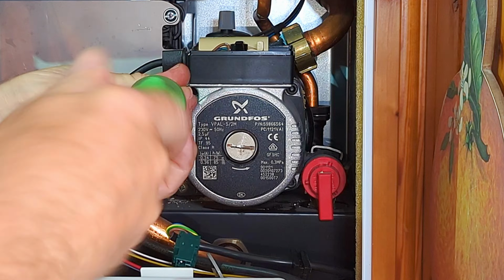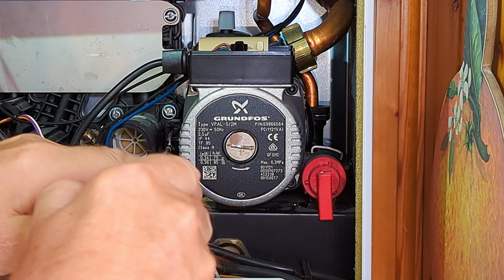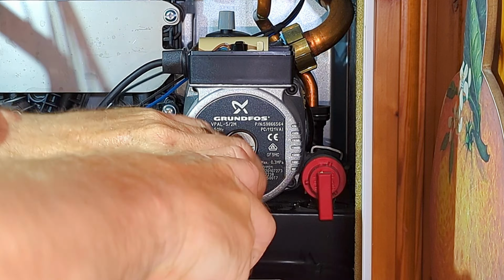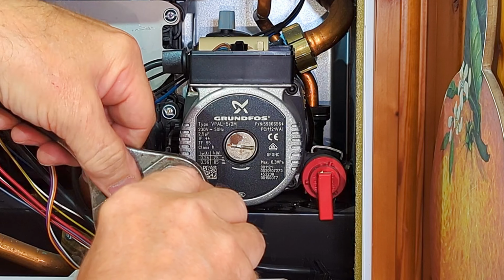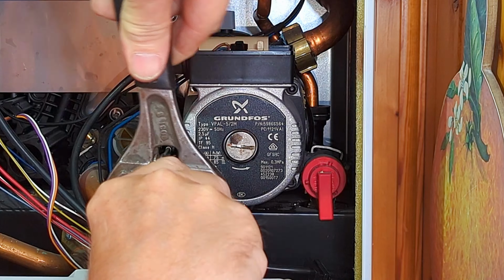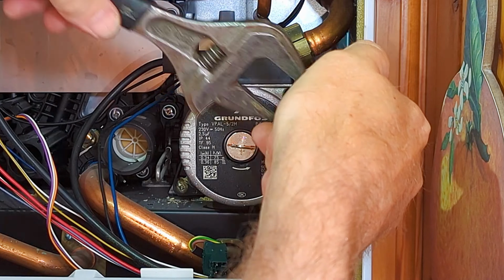Obviously, before we fit the new pump, we need to remove the old pump. And that's just a case of undoing the 4 screws on the outside of the pump. Now these can be quite tight, as you can see, but once they're undone, the pump head should just lift off without anything else needing to be undone or removed.